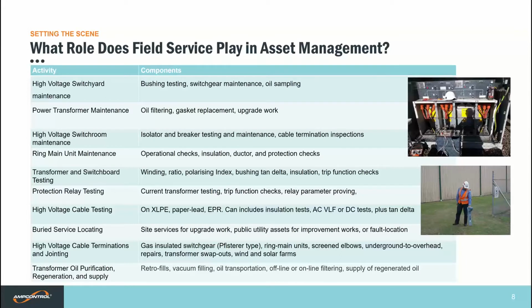What role does field service play in asset management? We've put up there a bit of a list of some of the activities that we do on a day-to-day basis locally throughout New South Wales and throughout Australia. High voltage switchyard maintenance, being bushing testing, switchgear maintenance, oil sampling, the power transformer maintenance, oil filtering, upgrade work, high voltage switch room maintenance. These can be the isolators and circuit breaker testing and inspection on cable terminations.